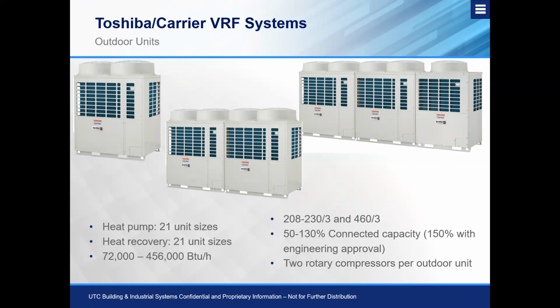And unlike the Carrier system, we are utilizing 2 rotary compressors per outdoor unit on the Toshiba Carrier system. That adds that nice redundancy, a little bit better low ambient heating capabilities, and then a nice technology that will balance the runtime between compressors. So for example, if we were to look at compressor 1 running from 8 to 12, the system realizes that that compressor has run from 8 to 12. And now it's going to say, hey, I'm going to run that second compressor from 12 to 5 to get equal runtime, which in turn generates a longer lifespan and equal runtime for those compressors versus a non-traditional inverter-based system.